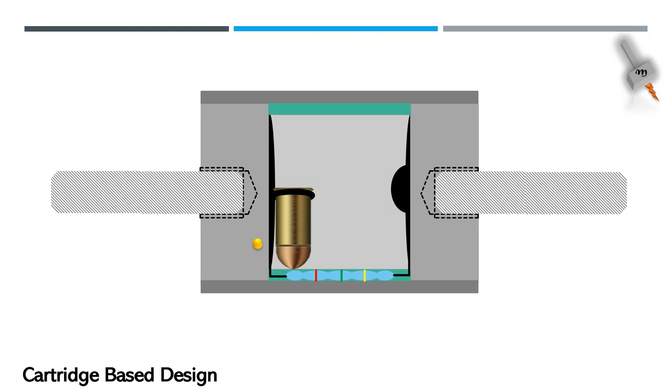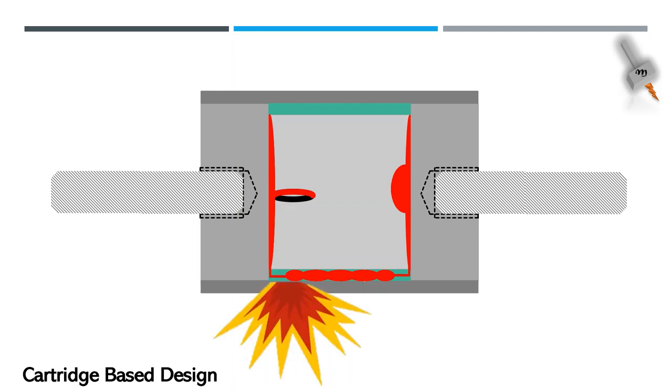Under normal duty, the leakage current flows through the wire wound resistor, indicated as the blue unit. Under surge condition, a higher amount of current flows through the resistor, thereby increasing the voltage drop across the spark gap, thus causing the spark gap to transfer most of the fault current to earth. If the duration of the fault current lasts longer, then the spark assembly and the resistor get heated, thus activating the cartridge. The cartridge then blasts off the disconnector assembly, making visible permanent disconnection.